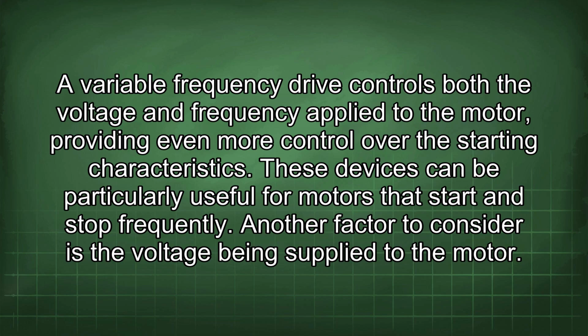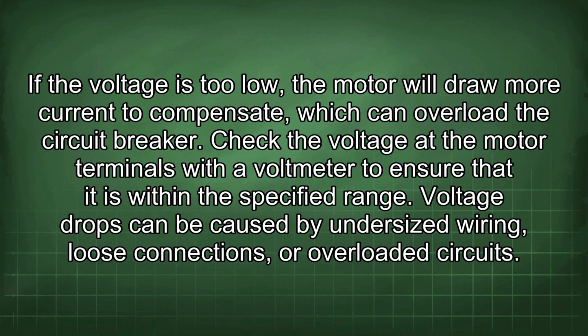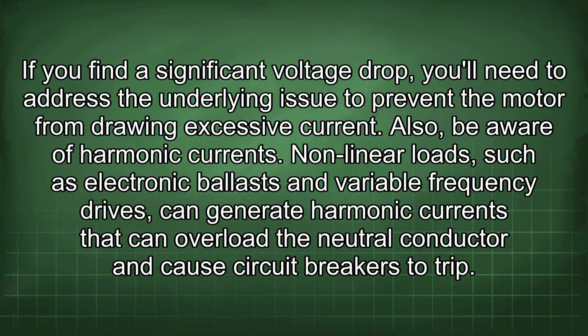Another factor to consider is the voltage being supplied to the motor. If the voltage is too low, the motor will draw more current to compensate, which can overload the circuit breaker. Check the voltage at the motor terminals with a voltmeter to ensure that it is within the specified range. Voltage drops can be caused by undersized wiring, loose connections, or overloaded circuits. If you find a significant voltage drop, you'll need to address the underlying issue to prevent the motor from drawing excessive current.